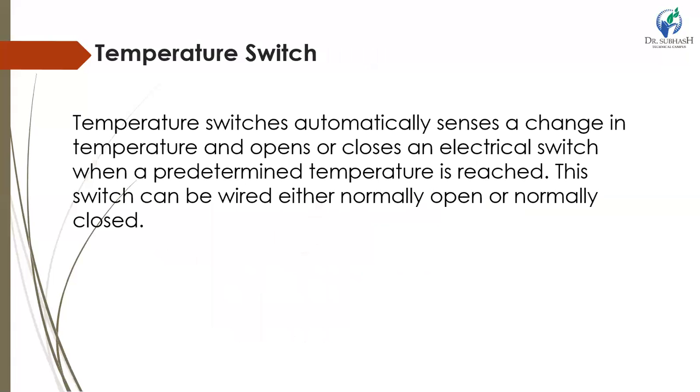Then the next one is temperature switch. This is the last point of this chapter. Temperature switches automatically sense a change in temperature and open or close an electrical switch when a predetermined temperature is reached. This switch can be wired either normally open or normally closed. Temperature switches can protect a fluid power system from serious damage when components such as the pump or cooler begin to malfunction. So this temperature switch is also used for safety purposes against heat.